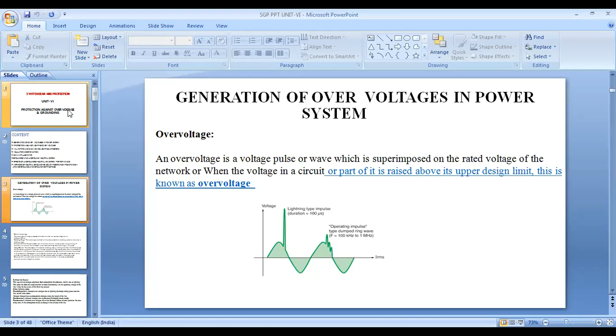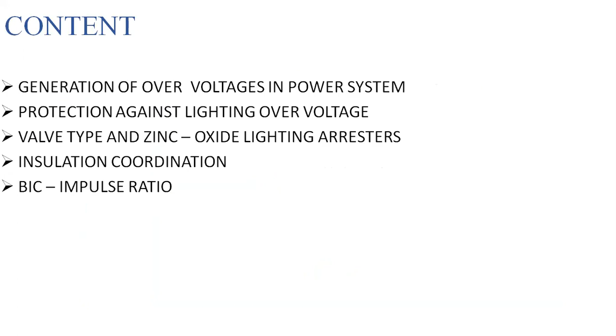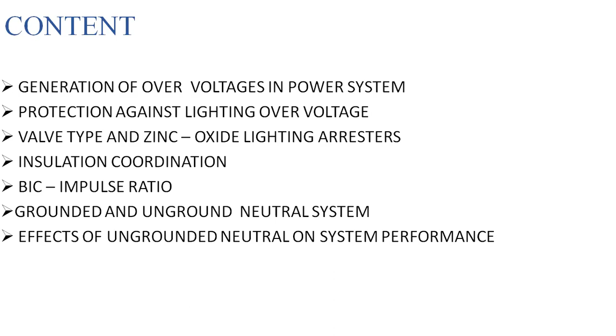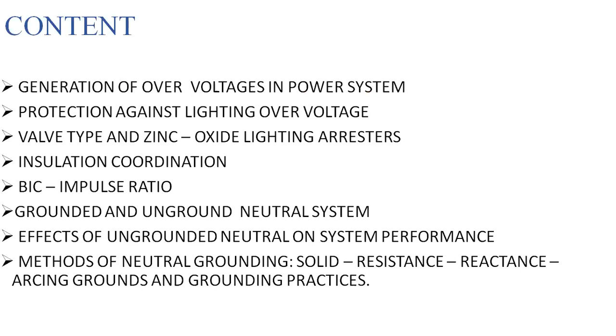Hi everybody. Now we shall discuss this last unit, protection against overvoltage and grounding. The contents I'm going to discuss are the generation of overvoltages in power system, protection against lightning overvoltage, valve type and zinc oxide lightning arresters, insulation coordination, V-t curve impulse ratio, grounded and ungrounded neutral system, effects of ungrounded neutral on system performance, and the methods of neutral grounding: solid, resistance, reactance, arcing ground, and grounding practices. So let us discuss the generation of overvoltages in power system.